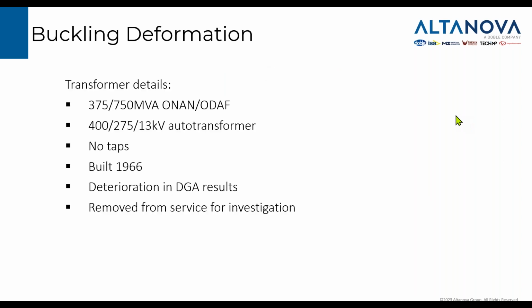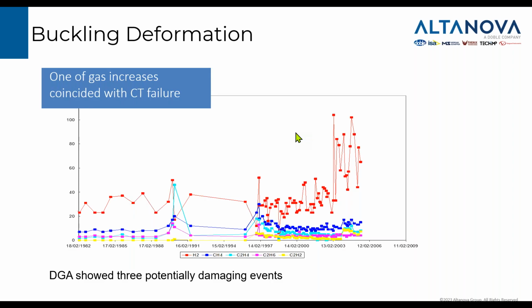Another example, large buckling deformation. In this case, we had a 750 MVA transformer, again an auto transformer, 400 kV to 275 kV with tertiary winding. There were no taps in this one. It was built in 1966, and deterioration in DGA results was observed over the years. It was removed from service for investigation.